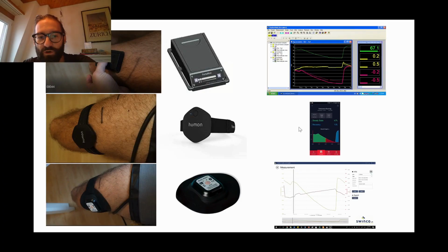But let's get to the meat of the situation. The first thing that I do when I get NIRS devices is complete occlusions. The reason I do complete occlusions is because you get a stabilized state where you should know what happens. So we know what should happen with a NIRS signal in a complete occlusion. I did the complete occlusion with the Portamon, with the Humon, and with the Moxy, and I'm going to compare those data points and see what it looks like. This also goes a little bit into the validation of NIRS, which I'll go into at the end: how validated is the technology, or the different devices, which isn't so easy to do, especially when we talk about the actual values and not just the trending.